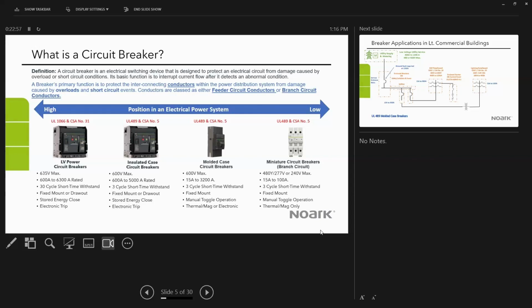So the only real difference in the insulated case breakers is they're tested to a three cycle short time withstand rating. And then moving on to molded case breakers, this is the next layer below the insulated case breakers. And this serves as the primary circuit protection device through the majority of the power distribution system. And these range anywhere from 15 to 3,200 amps. 3 cycle short time withstand, they're fixed mount, and instead of being stored energy, they have a manual toggle operation that I'm sure you're all familiar with.